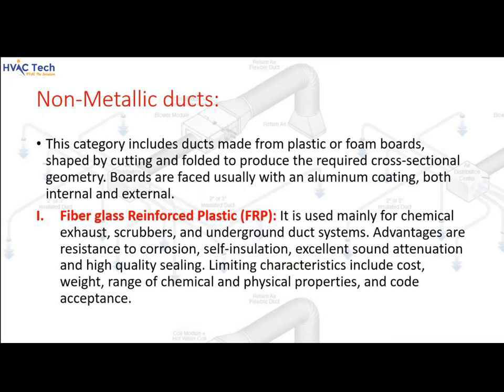Non-metallic ducts include ducts made from plastic or foam boards shaped by cutting and folding to produce the required cross-sectional geometry. Boards are usually faced with an aluminum coating on both internal and external surfaces. Fiberglass reinforced plastic (FRP) is used mainly for chemical exhaust, scrubbers, and underground duct systems. Advantages include resistance to corrosion, self-insulation, excellent sound attenuation, and high-quality sealing. Limiting characteristics include cost, weight, range of chemical and physical properties, and code acceptance.